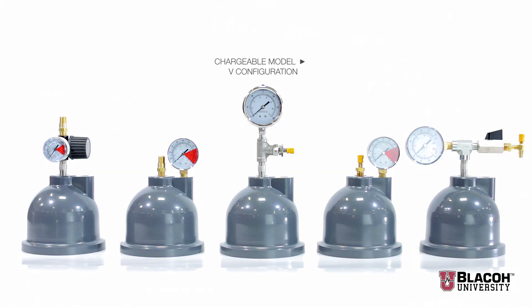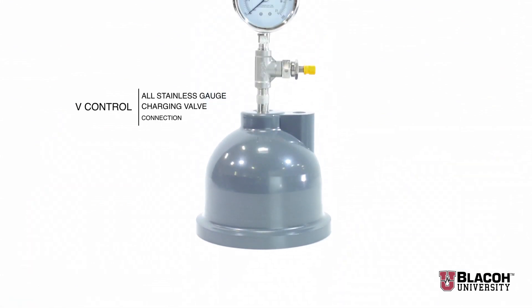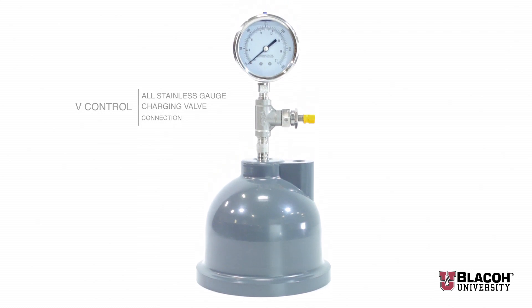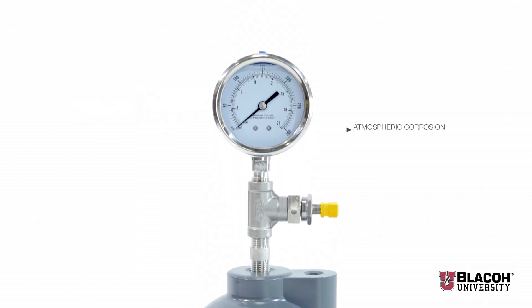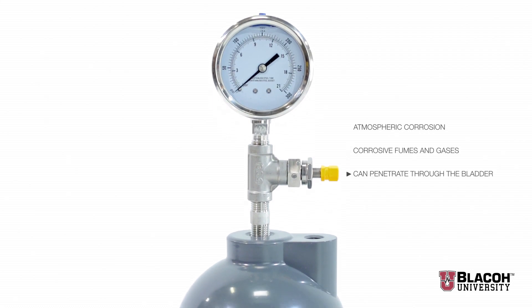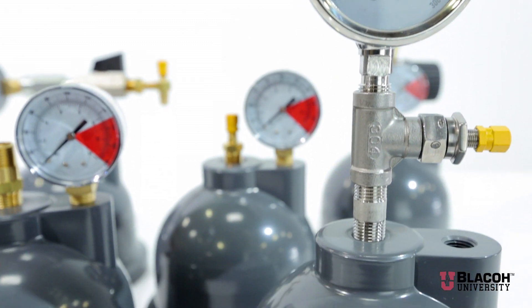Also available as an option is the chargeable model in what Blacoh calls the V configuration. This V configuration has an all stainless gauge, charging valve, and connection. This V control is essential in applications involving atmospheric corrosion and where corrosive fumes and gases can penetrate through the dampener bladder and corrode brass control components from inside.